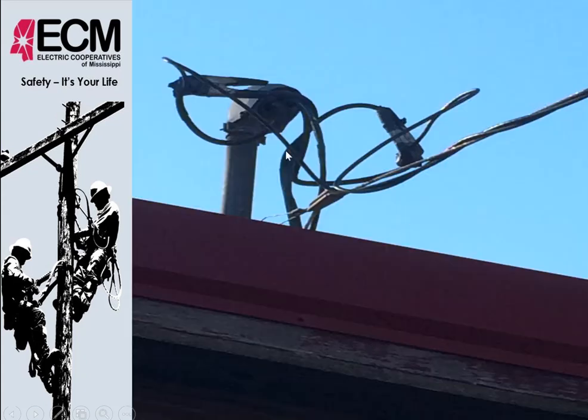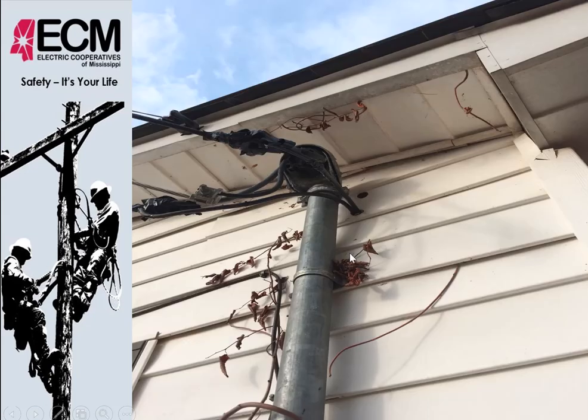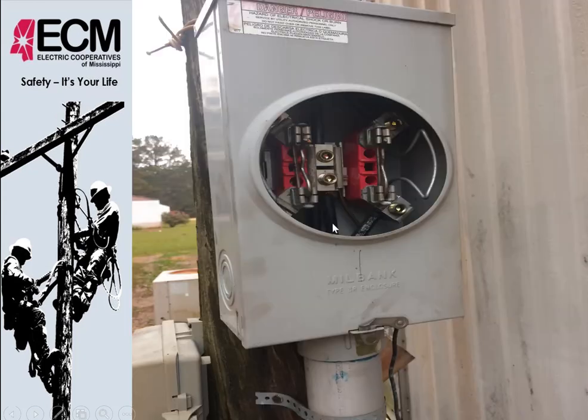Okay. Jumper cables right here, got this service jumped out. Got the jumper cables there run down probably to the bottom side, the load side of the meter socket. Okay. This is something to pay attention and be aware of. Got your entrance cable coming here and going to the weather head, but they've taken and run some wire inside the building, inside the house, that comes off above the meter. Okay, so just borrowing a little bit. Okay, so make sure that that's not like that.